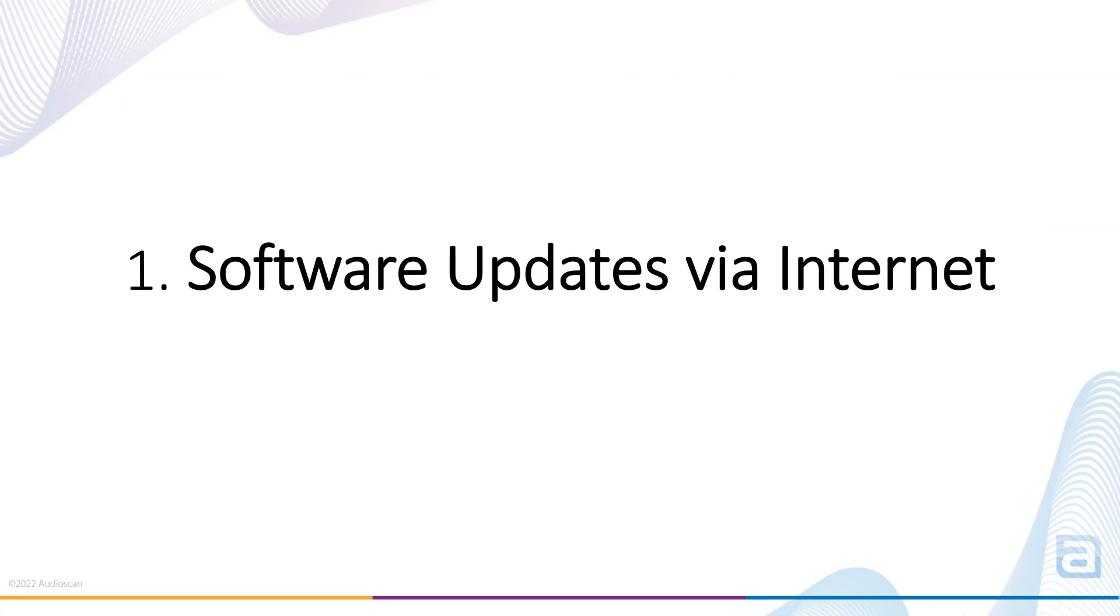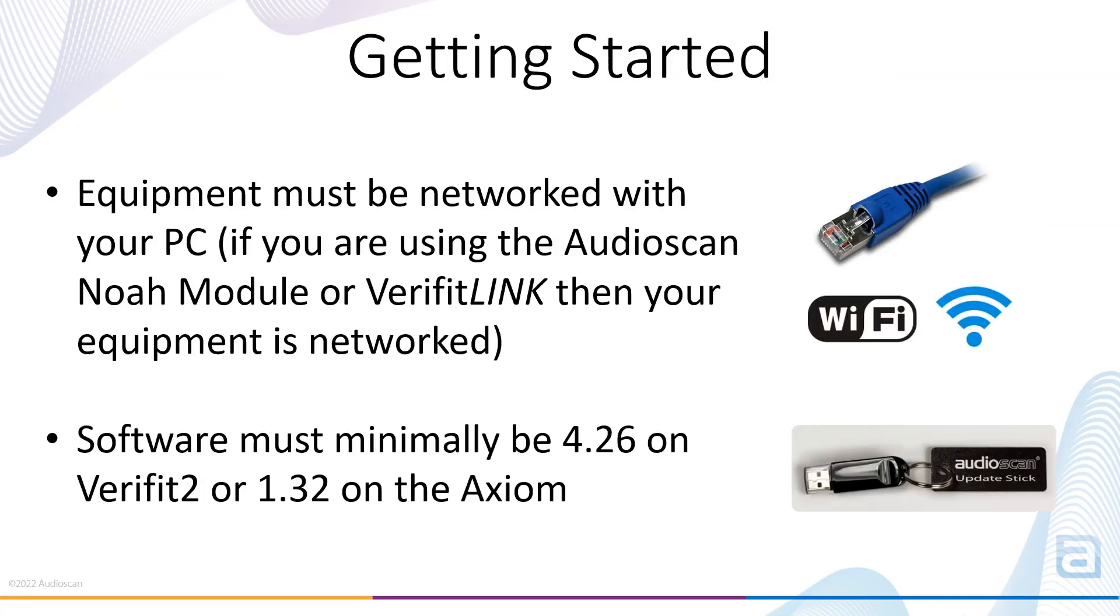Software updates via internet. For this feature, equipment must be networked via Wi-Fi or an ethernet cable, and the internet must not be blocked on the PC. If you've updated your equipment software in the past year and your Verifit 2 is at 4.26 or later software, or Axiom is at 1.32 or later software, then the equipment can be updated via the Audioscan Noah module.